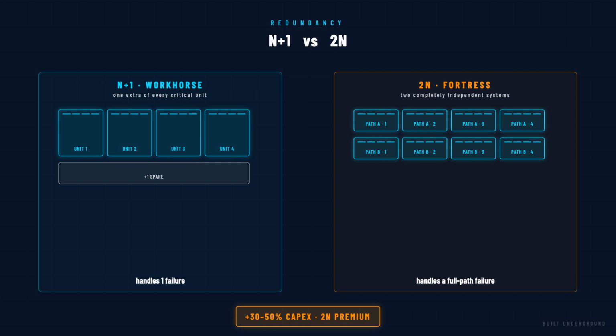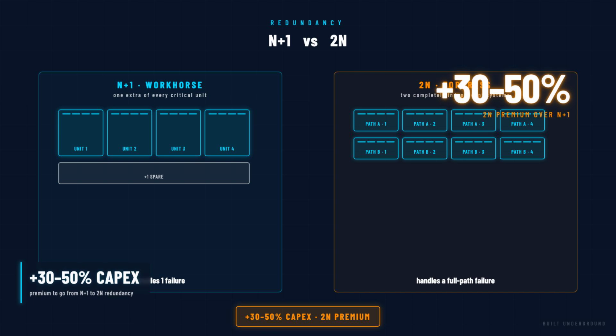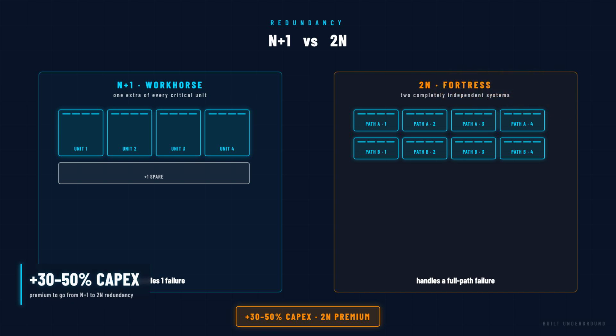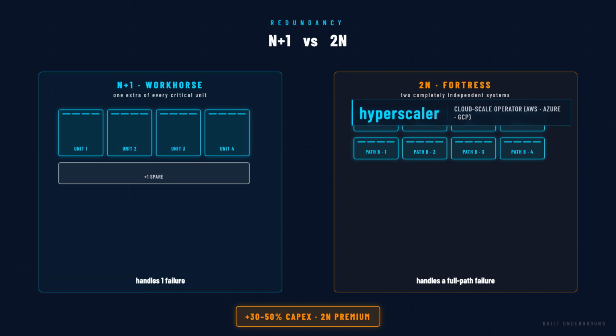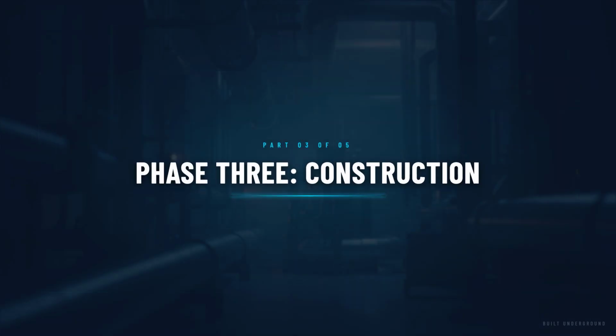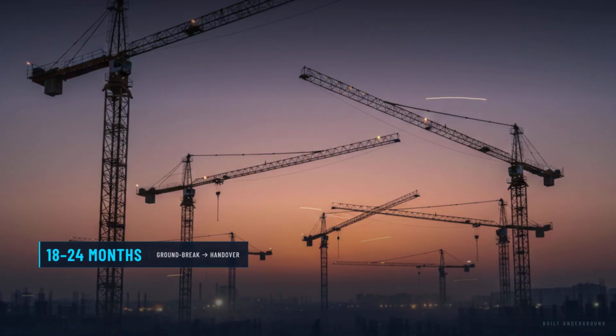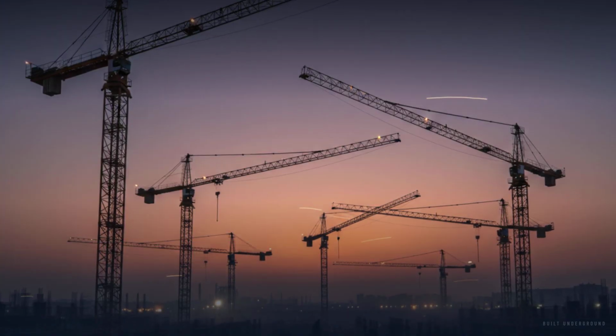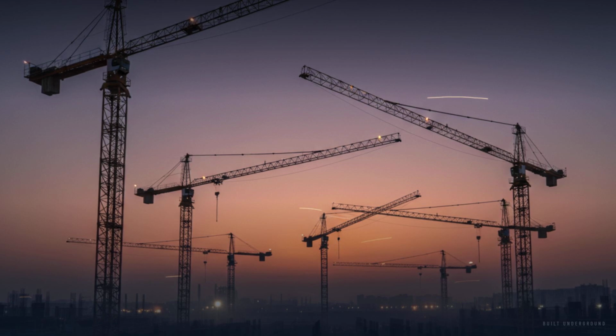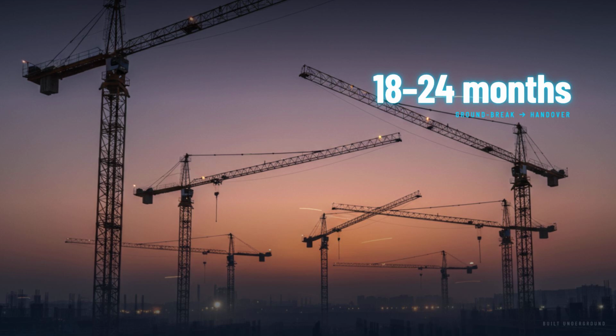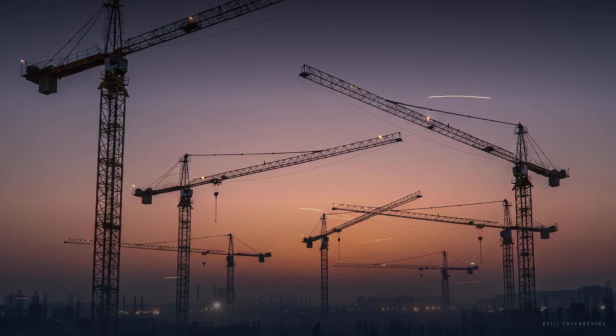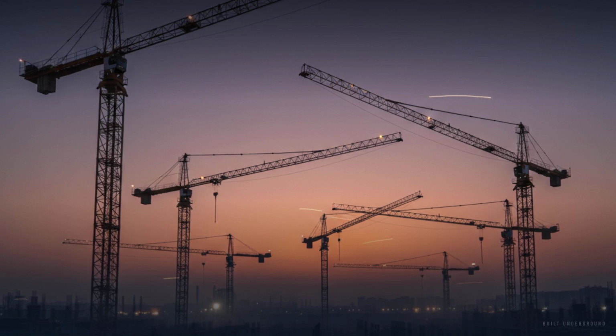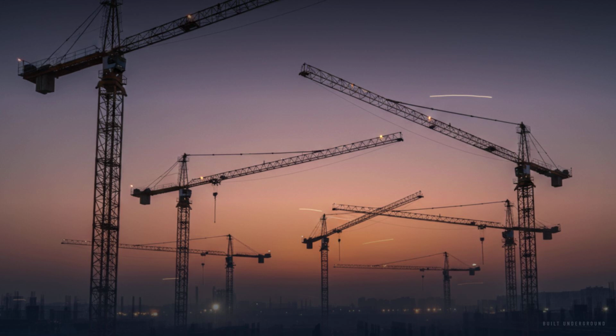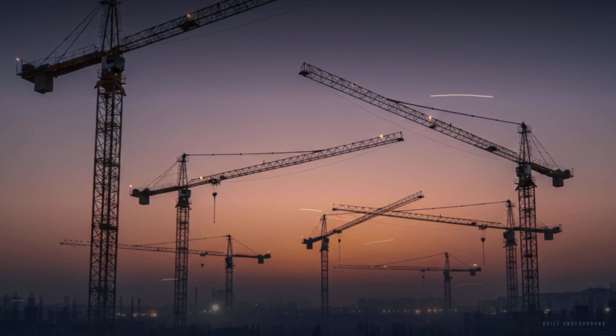The difference between N+1 and 2N can add 30 to 50% to the construction cost. But for a hyperscaler running billions of dollars of cloud services, a single hour of downtime can cost more than the entire redundancy premium. This is where the building comes to life, and it is a process most people never see. A typical large data center build runs 18 to 24 months from groundbreaking to handover.